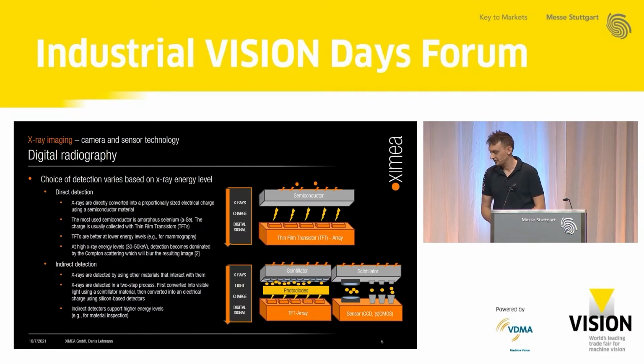There are various detector types. Two prominent ones are the flat panel arrays, which have big pixels, large field of view, but they suffer from speed usually, so they're not that fast, and they don't have a very good resolution. So X-ray cameras, instead, have a high resolution, they have an excellent speed, especially the newer ones. And if you combine it with a taper, to which I will come later, you also have a big field of view, so it's kind of a good compromise.